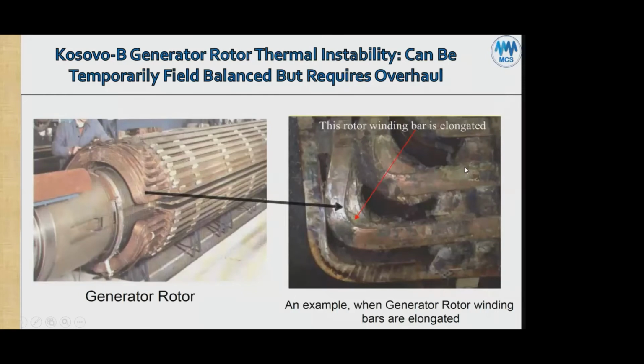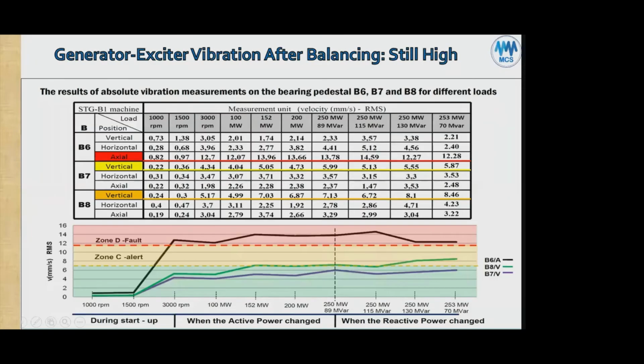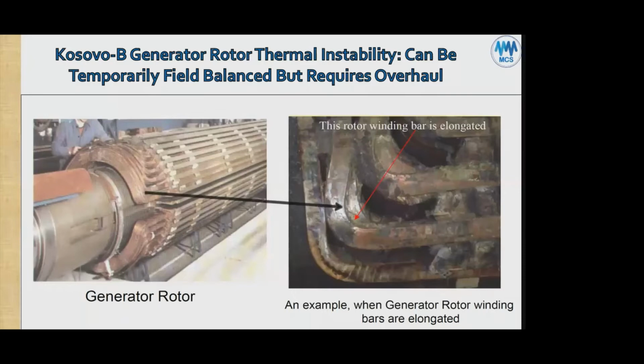Because of this vibration, they expected there was something wrong with the generator itself, and they realized they were going to have to solve it. So they took it apart and found the generator rotor winding bars are elongated. If you come up with this situation, either you do a temporary field balance until you can overhaul it, or you go in and put in the spare rotor. Hopefully you have a spare generator rotor and you use that. If you don't have a spare generator rotor, then you have to fix it. But sometimes this can be balanced in place. It solves the problem temporarily. Not fully balanced, partially balanced. Okay.